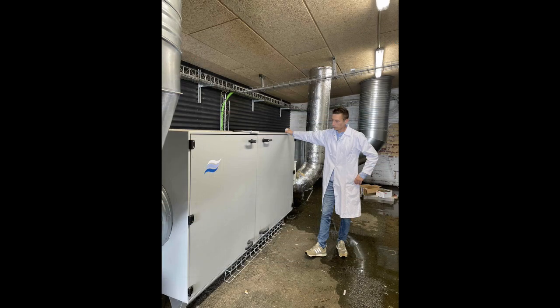Yeah, that's a really good question, and again, very topical. Well, as I just mentioned, the type of technology that we're using in this application is a desiccant dehumidifier. And the main energy needed for this system is the heat needed to continuously remove water from the absorbent rotor. This drying process is called regeneration, and it literally blows the absorbed moisture from the dehumidifier to an external vent.